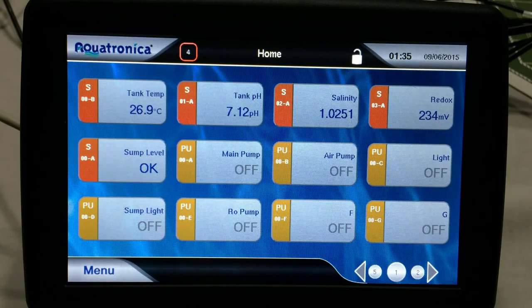But as I said, pH does take a few minutes sometimes to adjust. So it's closing down on roughly pH 7. So that tells you that you have a good calibration right there, and it's pretty much ready to go into the tank. I mean, we could sit here and wait for it to settle, but it might take another 2-3 minutes to settle down to 7 flat. So now I guess what I'll do is put it in the tank water that I had, and see what that's reading.